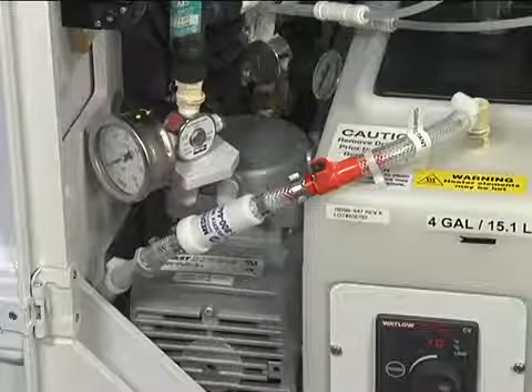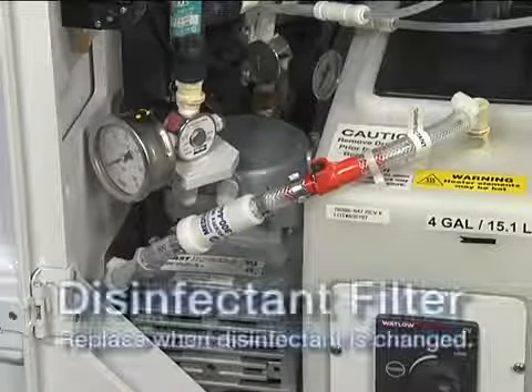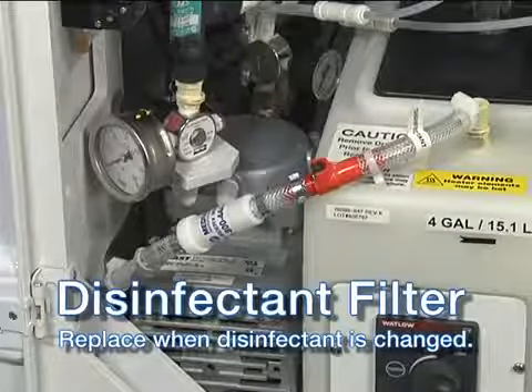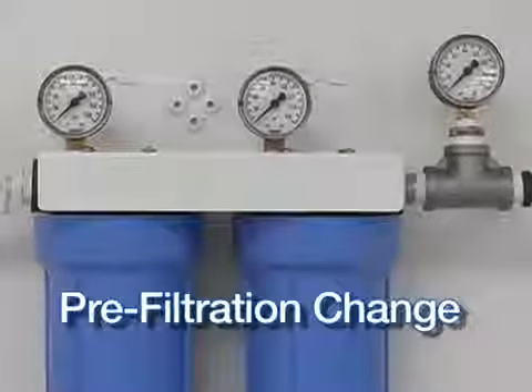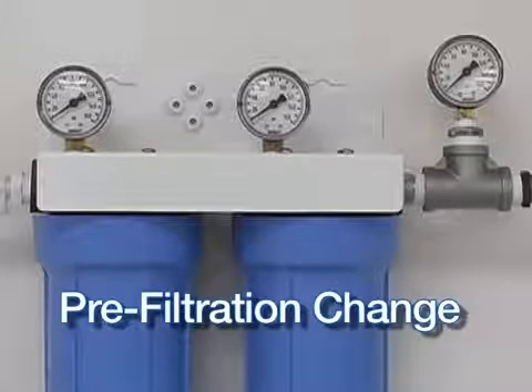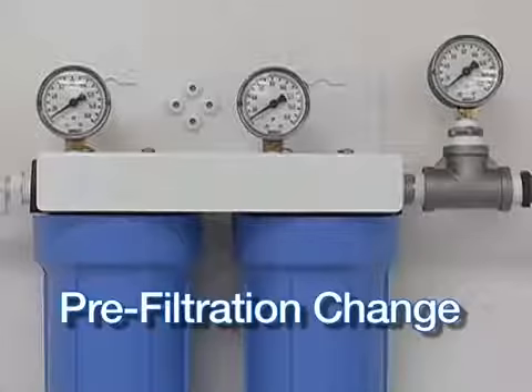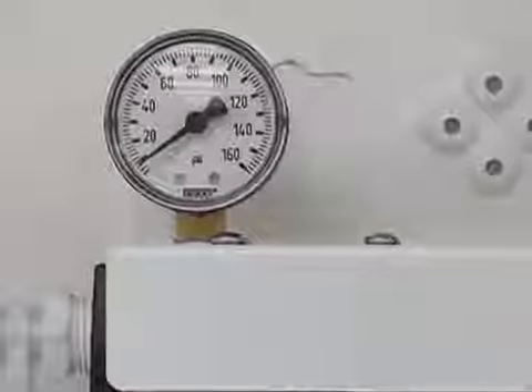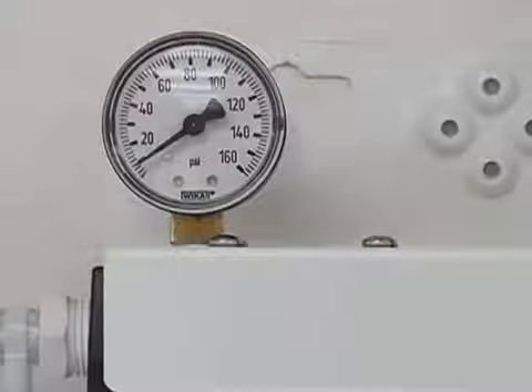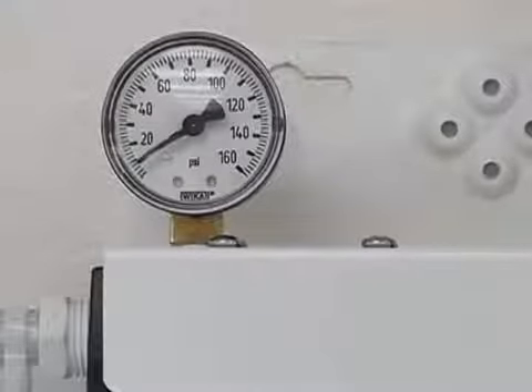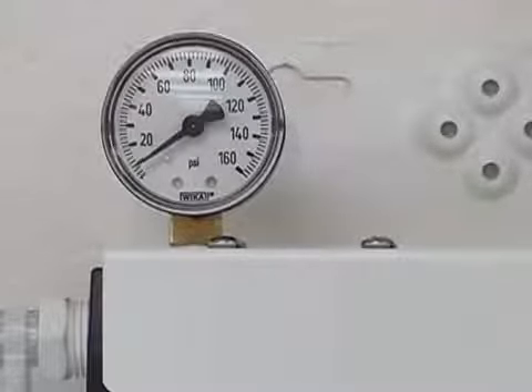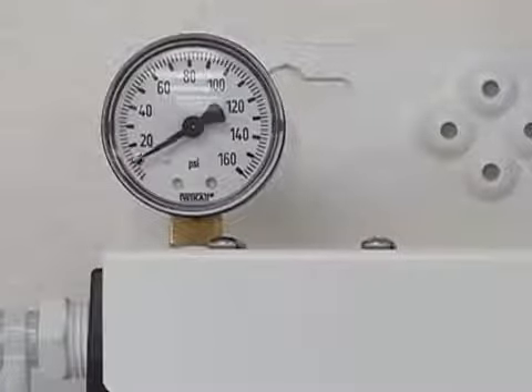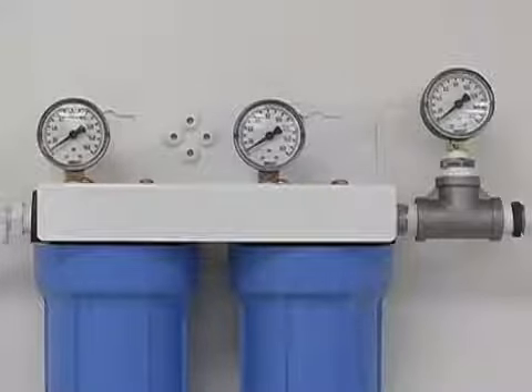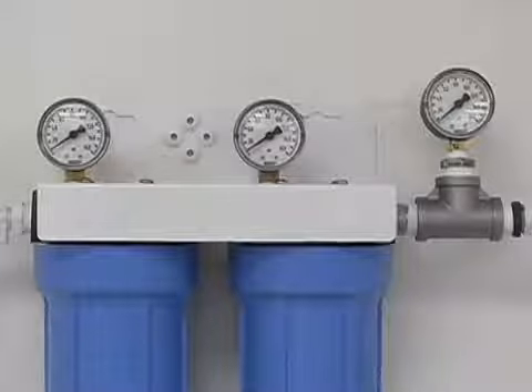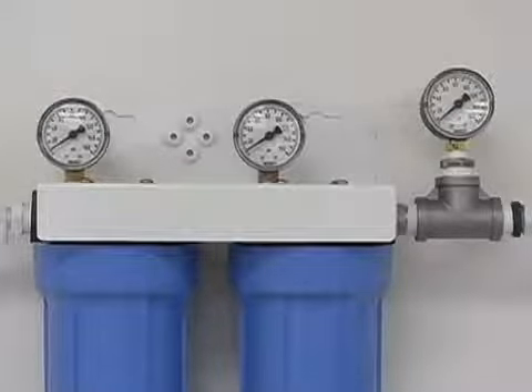Check when the disinfectant filters were last changed. These filters should be replaced with every disinfectant change. Water quality can vary geographically, seasonally, and intermittently, depending on a variety of factors, which will affect filter life. Saturation of the filters with sediment will reduce the incoming water pressure to drop below the minimum 40 psi requirement in the DSD-201's flush cycle. When this occurs, the difference in pressure between the gauges will indicate which filter must be changed.